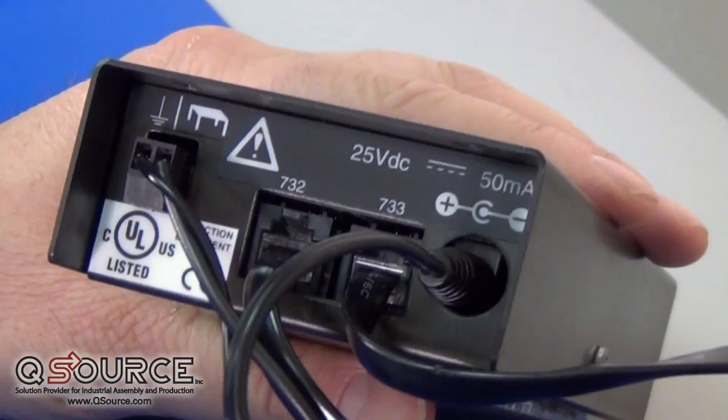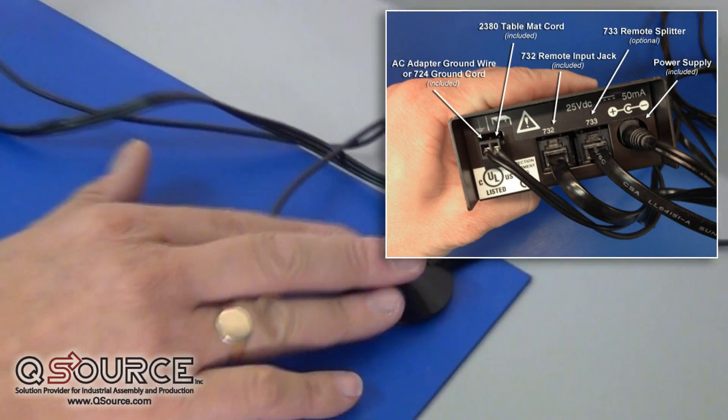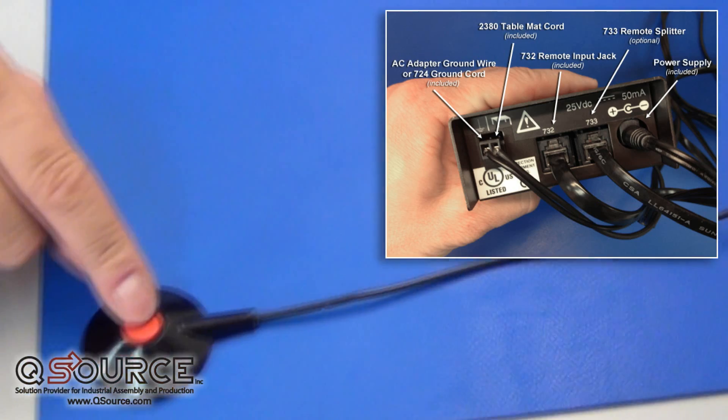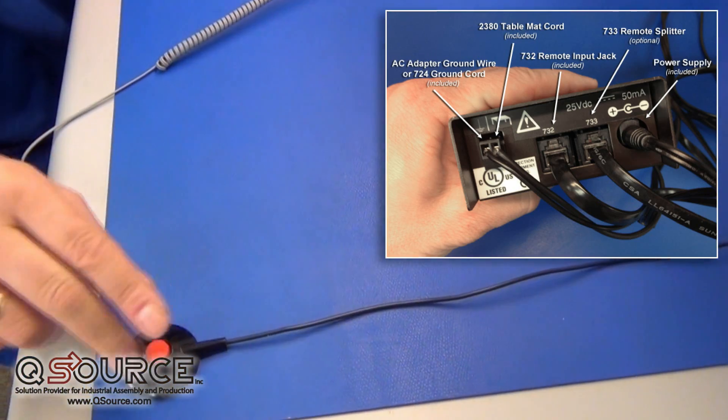To install the unit, you have to make sure that your mat or bench is grounded properly initially. The monitor then requires a second ground, which is here on the mat. So we have two snaps either on the bench work surface or on the mat.